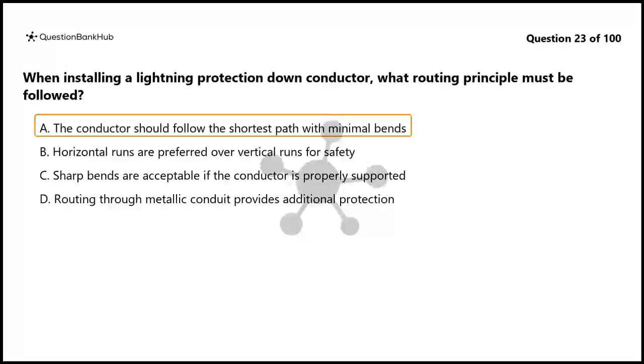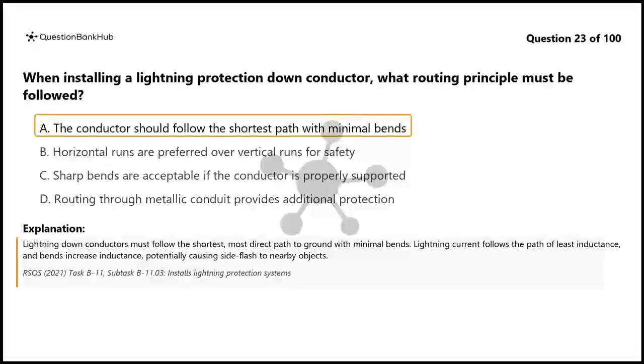The correct answer is A. The conductor should follow the shortest path with minimal bends. Lightning down conductors must follow the shortest, most direct path to ground with minimal bends. Lightning current follows the path of least inductance, and bends increase inductance, potentially causing side flash to nearby objects.